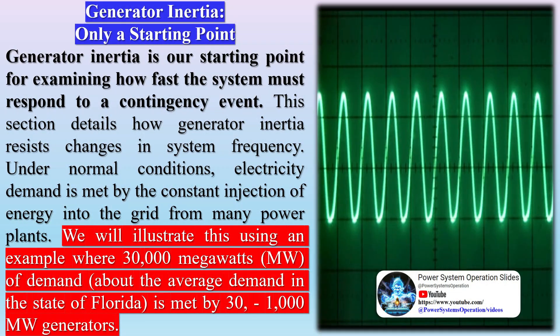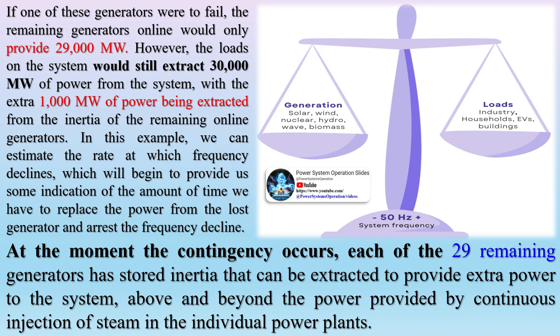Generator inertia is our starting point for examining how fast the system must respond to a contingency event. This section details how generator inertia resists changes in system frequency. Under normal conditions, electricity demand is met by the constant injection of energy into the grid from many power plants. We will illustrate this using an example where 30,000 MW of demand — about the average demand in the state of Florida — is met by 30 1,000 MW generators. If one of these generators were to fail, the remaining generators online would only provide 29,000 MW. However, the loads on the system would still extract 30,000 MW, with the extra 1,000 MW being extracted from the inertia of the remaining online generators.